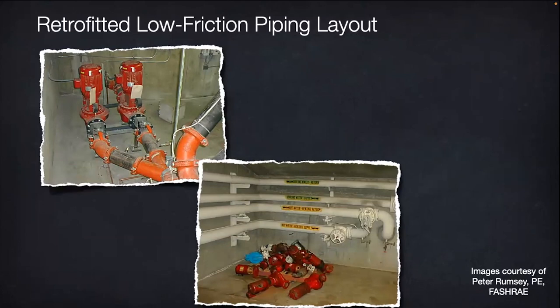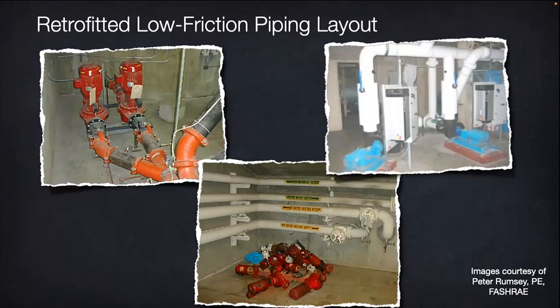Mega pumps are the best kind. Repiping the chilled water pumping loop and adding variable frequency drive then doubled the flow and saved 85% of the energy. Peter simply asked the pipe fitters to lay out the supply pipes as if they were drains.